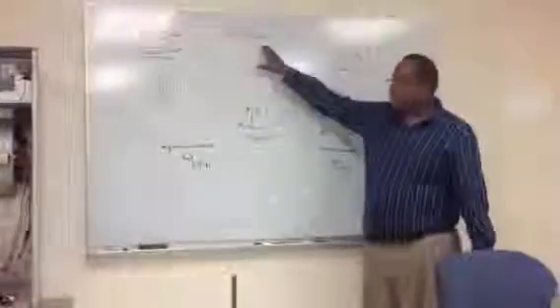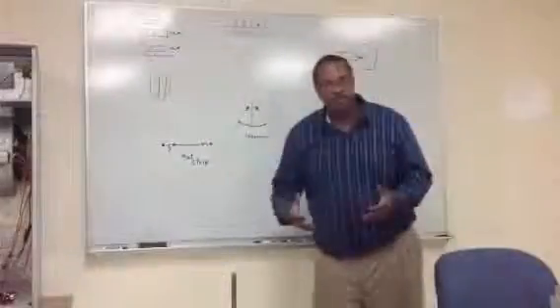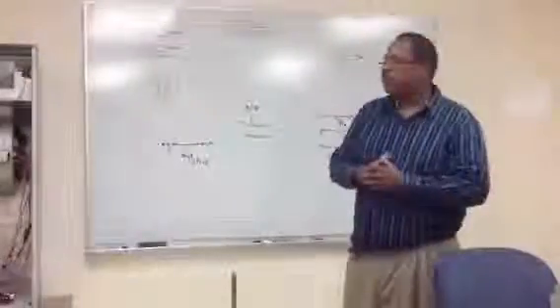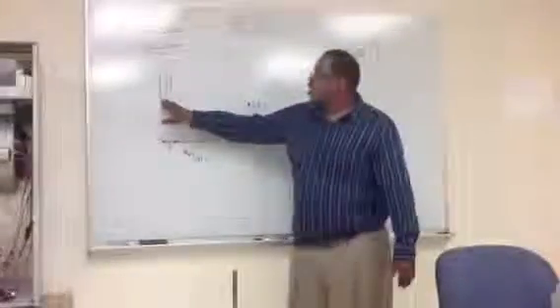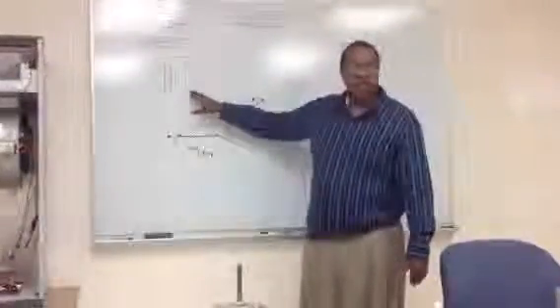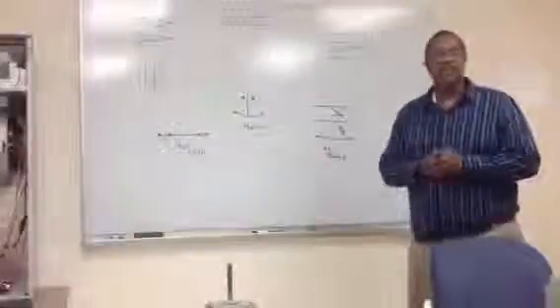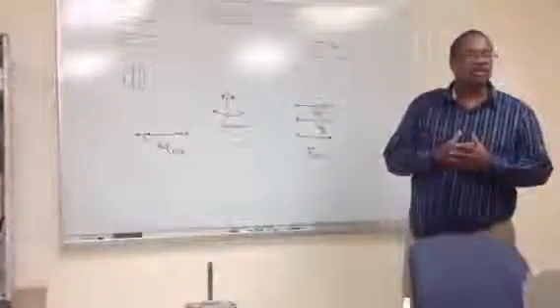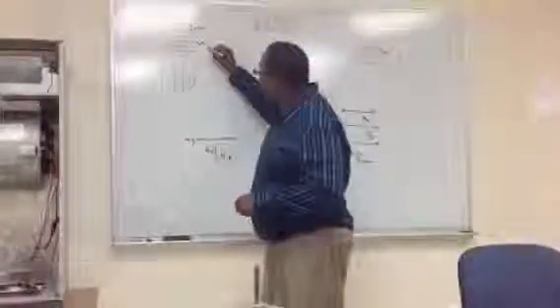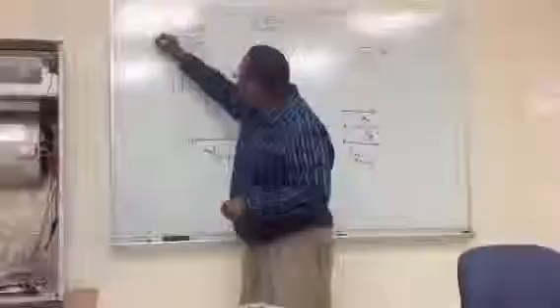The next thing in our low voltage, and we're talking about low voltage first, is our switch, the thermostat. But where does the power come from for the low voltage? Well, all the power comes from the main power of the building, or home, or whatever the case may be. But the transformer is what reduces that power. It takes the main power and steps it down to 24 volts. Now we know in electricity, as long as it is within plus or minus 10%, it's good voltage, we can use it. But if it's outside of that, then we can run into some problems. So let us get power over here to our transformer. Okay? Notice it has two legs of power to our transformer.